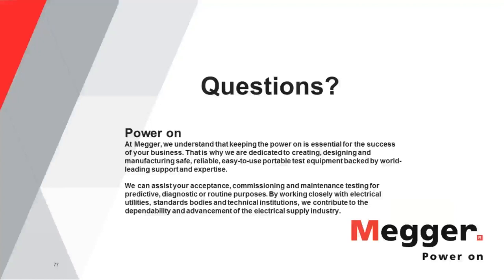Okay, thank you, Jeff. Next question is for Volney. Is the polarization index useful to determine if the insulation of a transformer is good? Okay, the polarization index depends on the material that you are testing being able to be polarized. And when you have oil, it doesn't polarize. So the values that you get when you test the transformer are very close to 1.